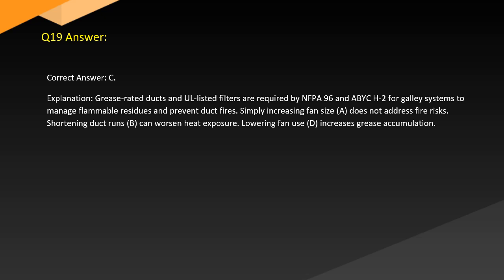Answer. Correct answer: C. Explanation: Grease-rated ducts and UL-listed filters are required by NFPA 96 and ABYC H-2 for galley systems to manage flammable residues and prevent duct fires. Simply increasing fan size (A) does not address fire risks. Shortening duct runs (B) can worsen heat exposure. Lowering fan use (D) increases grease accumulation.